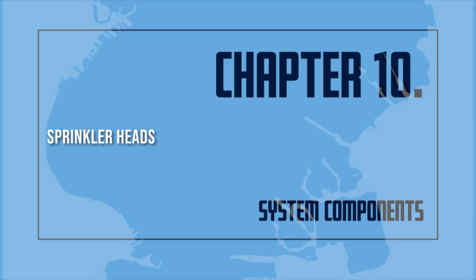There are over 50,000 different variations of sprinkler heads. Sprinklers manufactured after January 1, 2001 are required to have an SIN, or Sprinkler Identification Number. Sprinkler heads manufactured prior shall be replaced as required with sprinkler heads of similar characteristics such as orifice size, temperature rating, and deflector orientation. Recalled sprinkler heads.